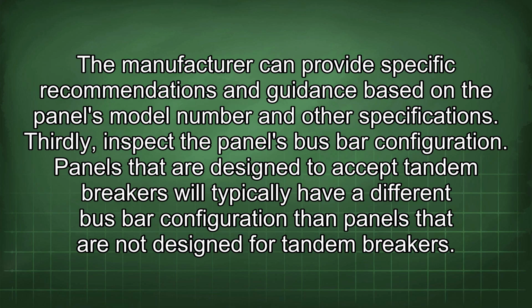Thirdly, inspect the panel's bus bar configuration. Panels that are designed to accept tandem breakers will typically have a different bus bar configuration than panels that are not designed for tandem breakers.